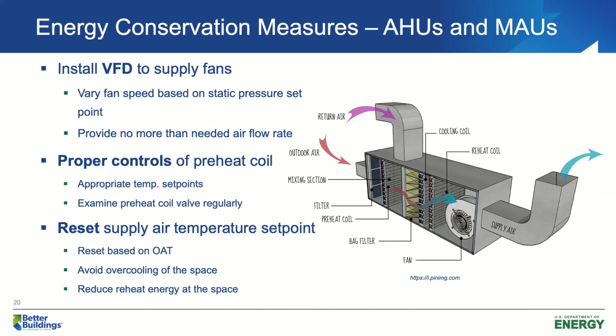Reset supply air temperature set point. We can reset the supply air temperature based on outdoor air temperature. When it is hot and humid outside, we can make the supply air a little bit cooler. When it is cool and dry outside, we can make the supply air a little bit warmer. This way we can avoid overcooled spaces, and we can have a better balance between fan energy and chiller energy.